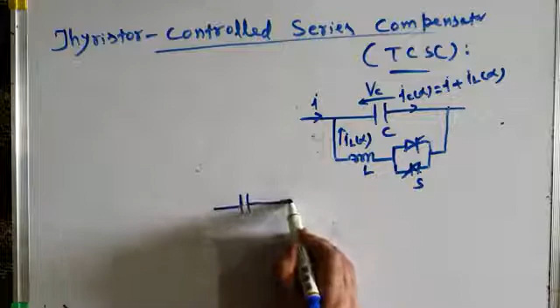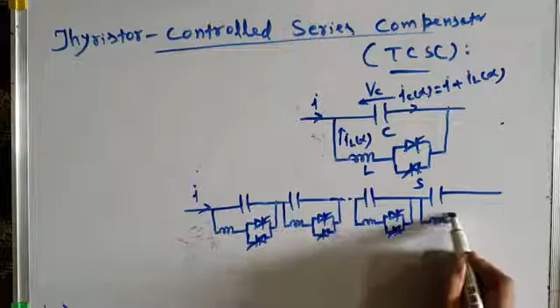Practically we do not have one TCSC in series with the transmission line. We have many TCSC units connected in series. It's something like this. For example, this is one capacitor, this is a second capacitor, so we can have many of these TCSCs in series. Similarly, then we have another TCSC, for example switch S1, S2, Sn minus 1, Sn. This is capacitor C1, this is capacitor C2, and so on, Cn minus 1 and Cn. Therefore TCSC basically is a series combination of many TCSC units. For series compensation of a transmission line, many TCSCs are connected in series like this. So this is practically how it is connected in the system.